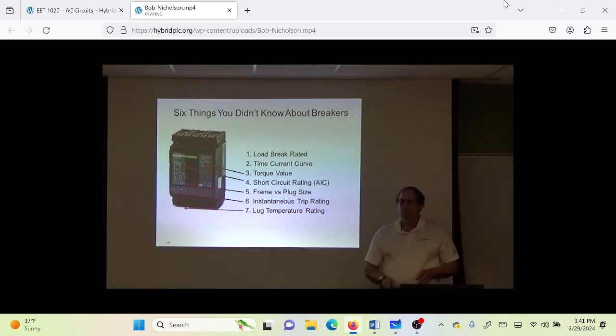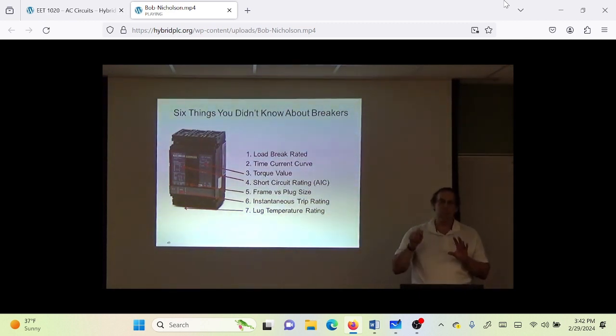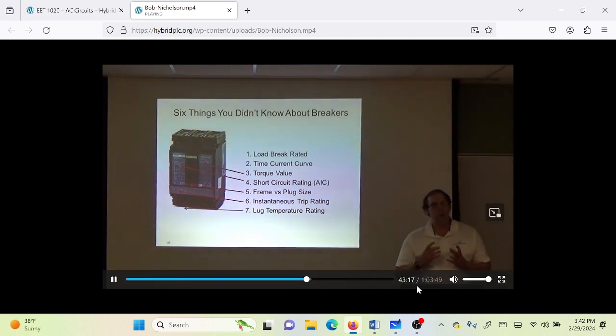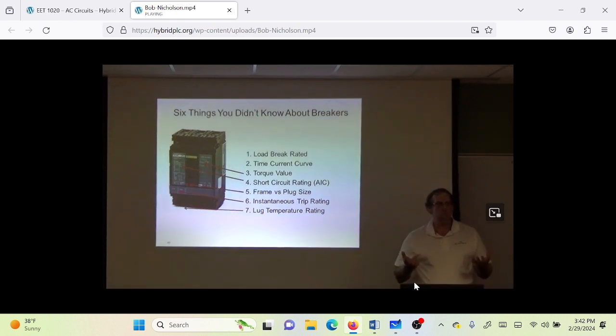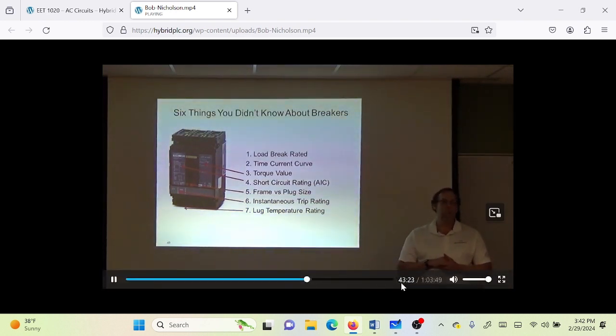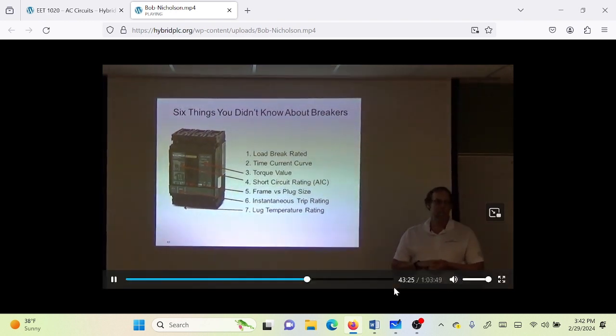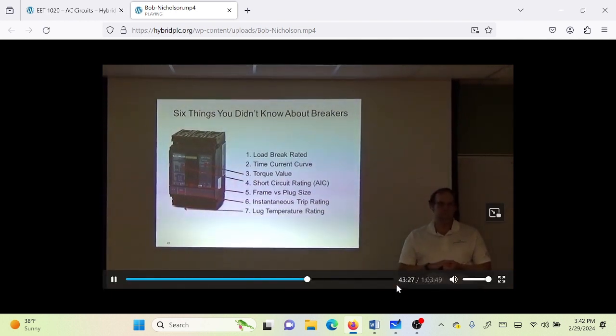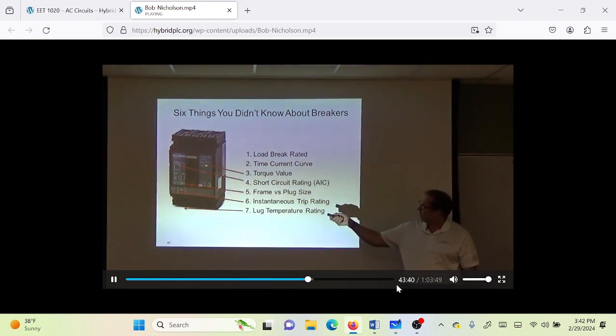First thing is, you better be careful opening things under load. If you open something under load, it has to be rated to open under load. Otherwise, it's going to explode. Now, how do things open under load safely? Very fast. Speed. Next thing, I'm going to show you what time current curves mean. You have no idea what these mean, but they control time. Torque value. You've got to be able to torque the wires down so that it's on the breaker.